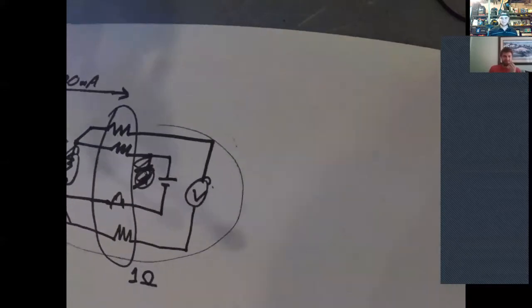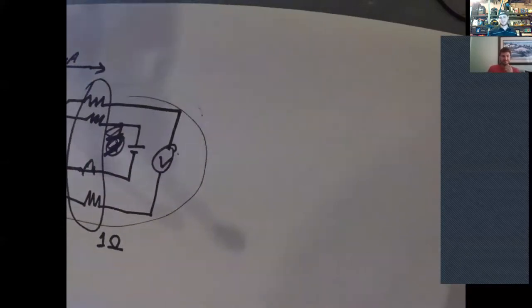So this configuration, which is called a bridge circuit, essentially allows you to measure at this voltage source only the change in this voltage. It's insensitive to, or at least once you calibrate it, basically all these wire lengths are the same and any temperature drift or any voltage drift from temperature change in these wires is essentially negated by this circuit configuration.